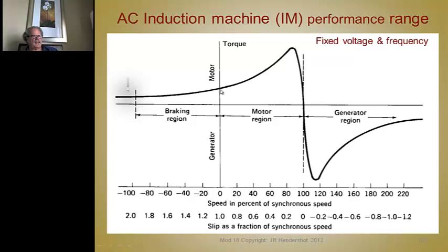Now when you start an induction motor under load, this is the starting torque. If you have a high resistance rotor, it'll put the starting torque up here, but then your slip will be greater. It'll slip like that, and so you won't run at very high efficiency up around operating speed. Now in generating mode, what you do is you crank the motor faster than the synchronous speed, and so now you have a negative slip instead of positive slip. And so you're really exciting the motor, but you're getting more power out than you're putting in.